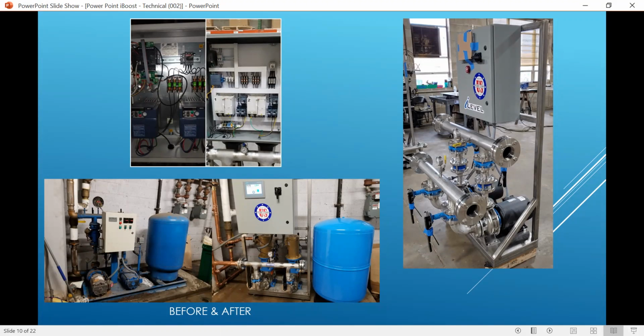If you've got a job, you send us the original drawing or the original conditions. I mean, we get it. I'll be honest with you. If you're a good booster manufacturer, you should be able to size the system with no information. You should be able to go out, look at the building, get a fixture count, get a building height, get your suction pressure read, and you should be able to design a system for that building. And that's kind of where we are.